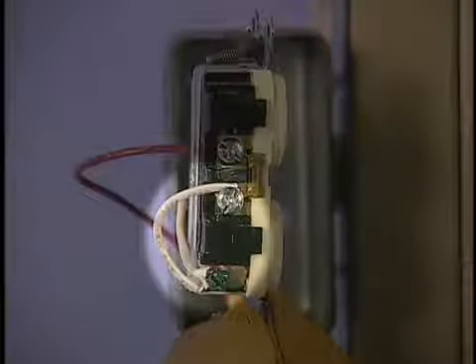Some electricians may not understand why neutrals must be isolated from ground until reaching the service entrance point. Others may not be familiar with the code. An attitude sometimes expressed is, since neutral is bonded to ground at the service panel, why not here too? Hopefully, this video is explaining why not: fire and shock hazard, as well as interference with electronic equipment, such as computer monitors. Let's look at another common source of area magnetic fields, created this time by miswired three-way switch circuits.